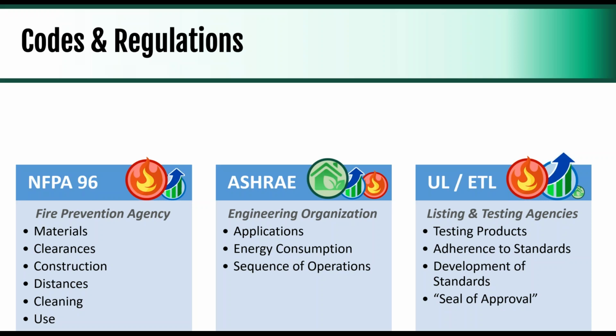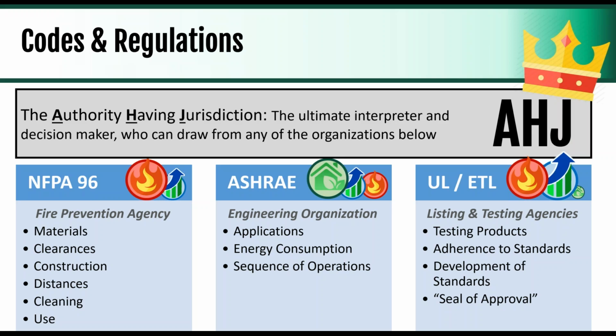UL actually develops the standards and tests to them, whereas ETL only tests to standards. So that's the difference between UL and ETL, but there are some other things we'll talk about too. And the last, and really what I put the crown on there because they have the final word, is the AHJ. That's the authority having jurisdiction. So while all these other organizations put out codes and standards, the AHJ is really the ultimate interpreter and decision maker, and can look at their requirements uniquely. Most of them are pretty in line with what we view, but there are some that are more onerous than others, which we've worked with in the past.